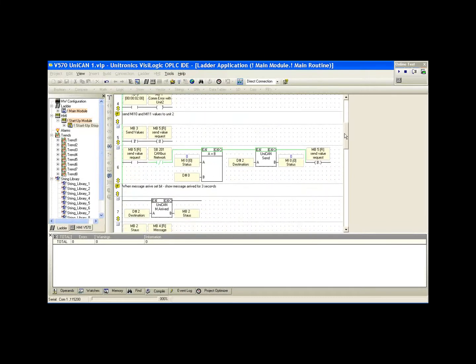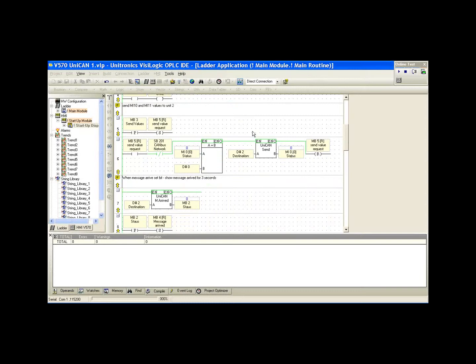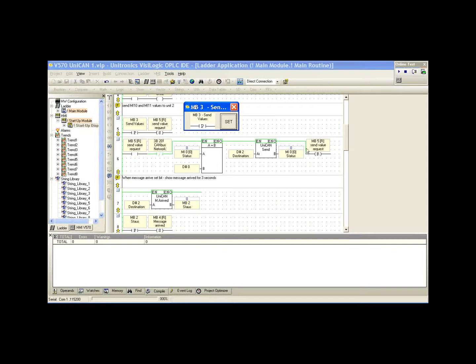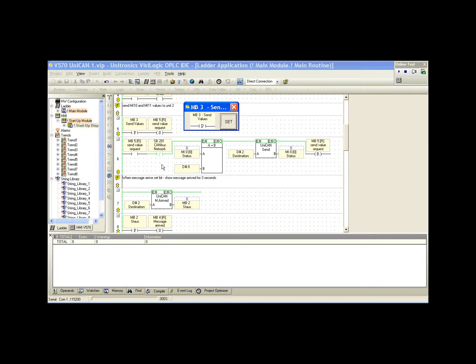The next function we're going to look at is the UNICAN send. MB3 is the button on the HMI, the send button. You'll notice the structure from all of our communication protocols, Modbus if we looked at that protocol. We're going to set MB5. MB5 is our send value request. MB5 will be set and stay high until we perform this network and reset MB5. Why do we do that? We do that because in the case of network traffic, a situation where we can't send a message, we don't simply want this message request to go away, we want it to wait for the next available opportunity to send a message.